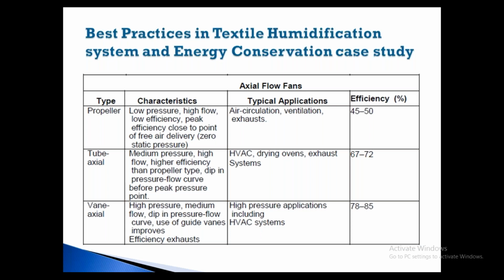Tube axial, you have a tube surrounding the impeller, with a distance of about 1 meter like that. So it is also a good efficient fan, 67 to 72%. This is also mostly used. And vane axial fans are not much used in our application.